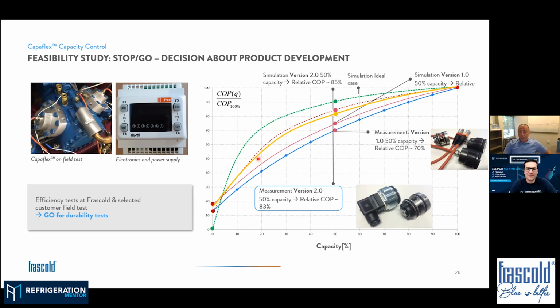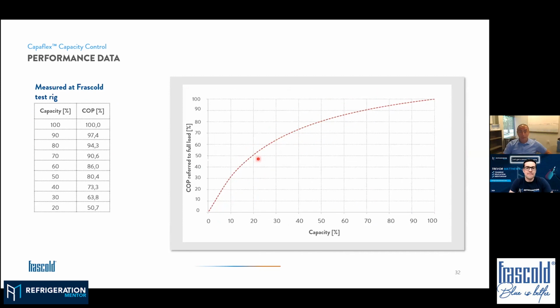So after the measurements, we obtained these tables that we usually share with customers to show what the technology is capable to do. Of course, the 0 is a theoretical value because we consider 20% as the minimum capacity step. If you go lower than that, you can run into lubrication issues or overheating issues potentially, whatever it is. It's something you want to keep in a safe environment.